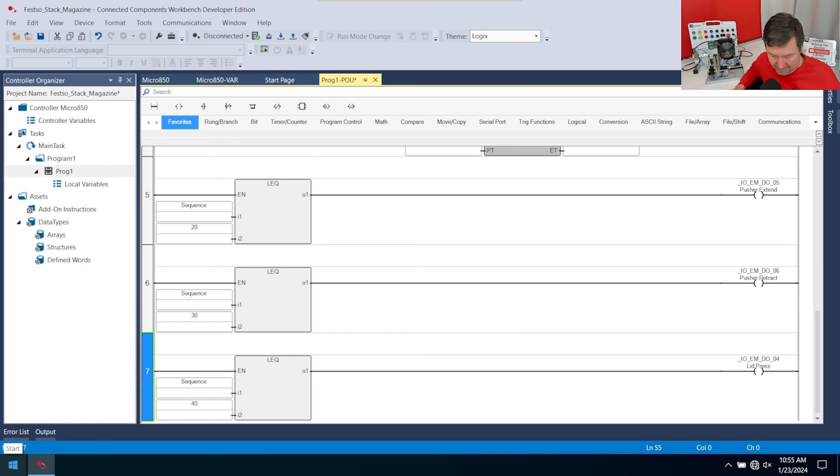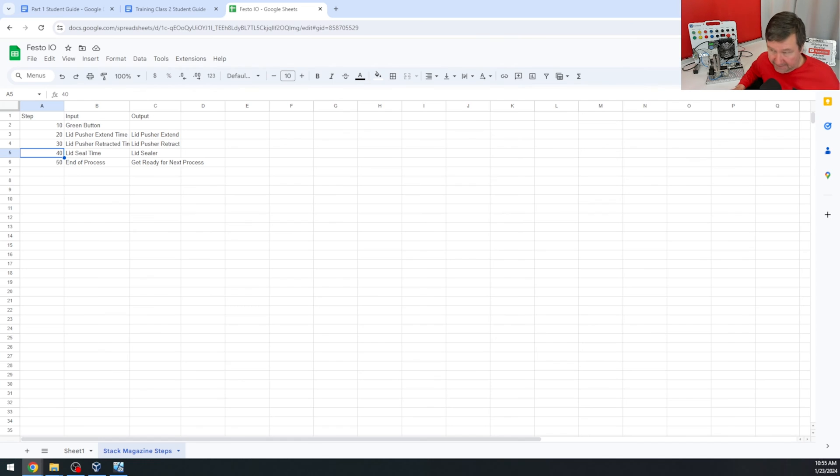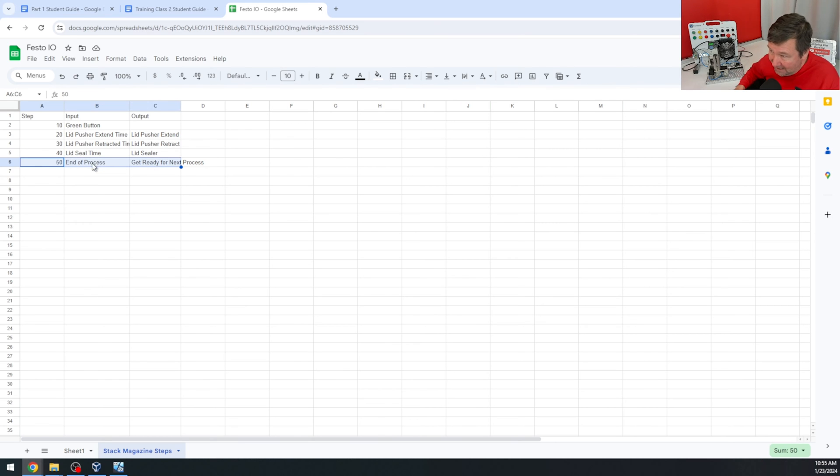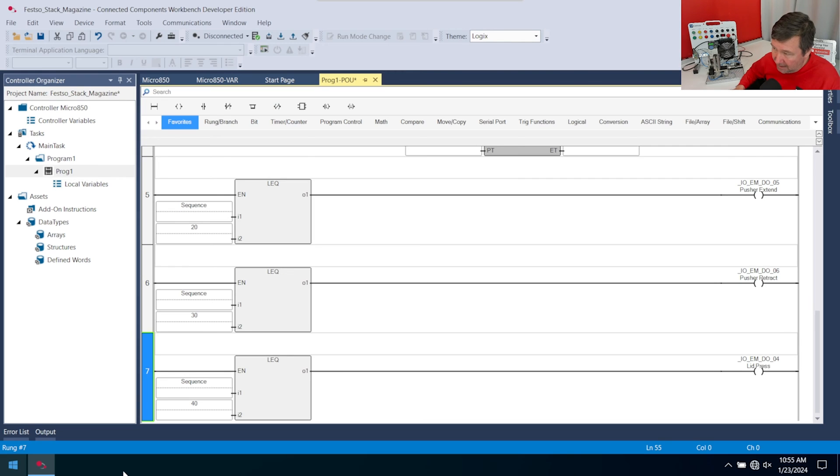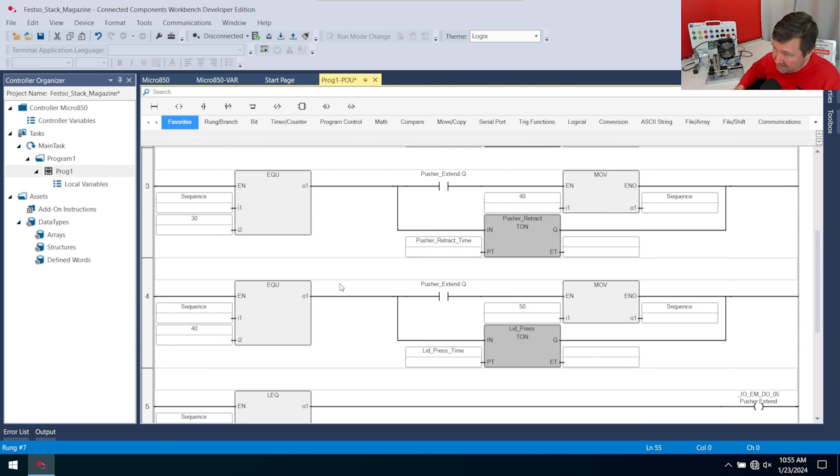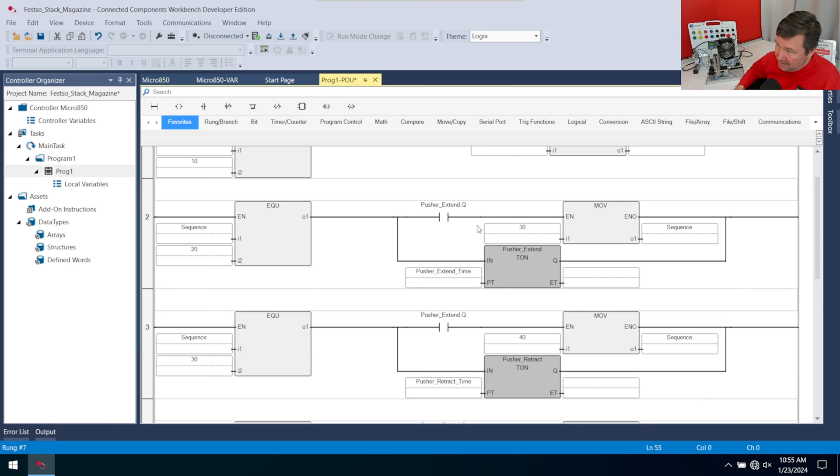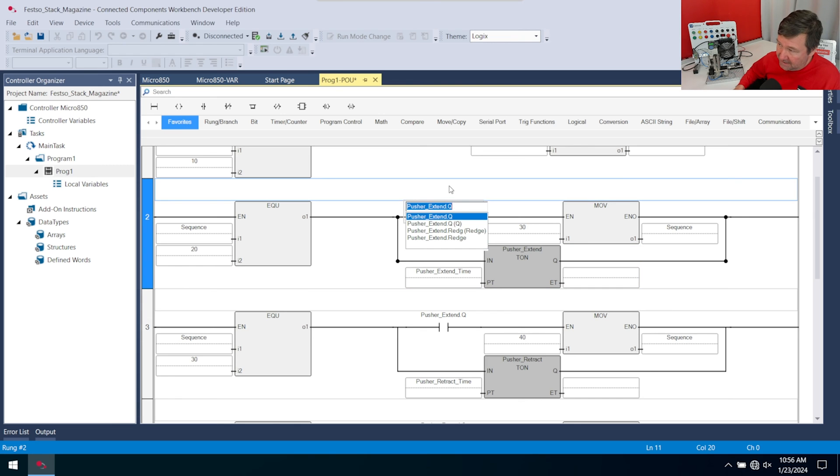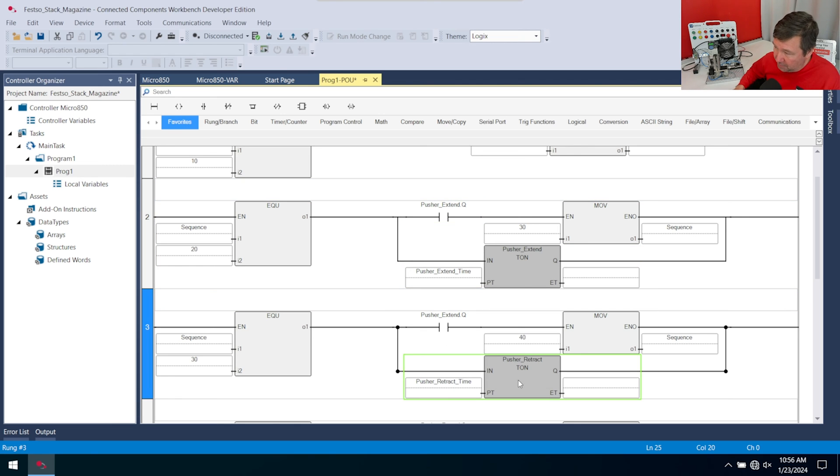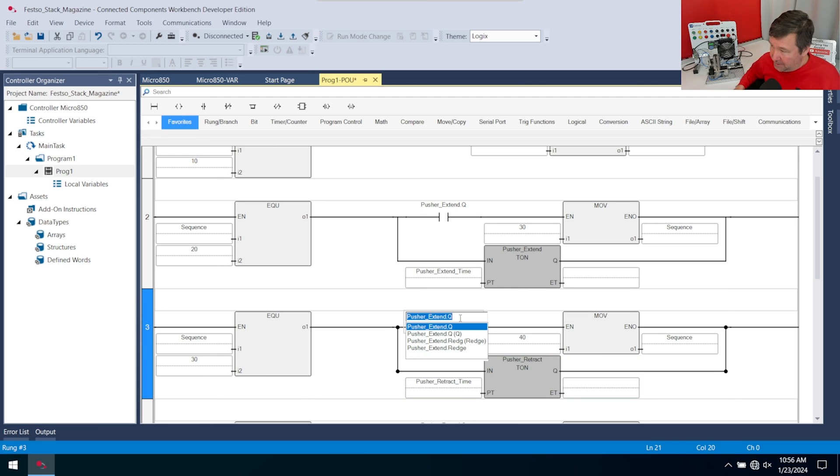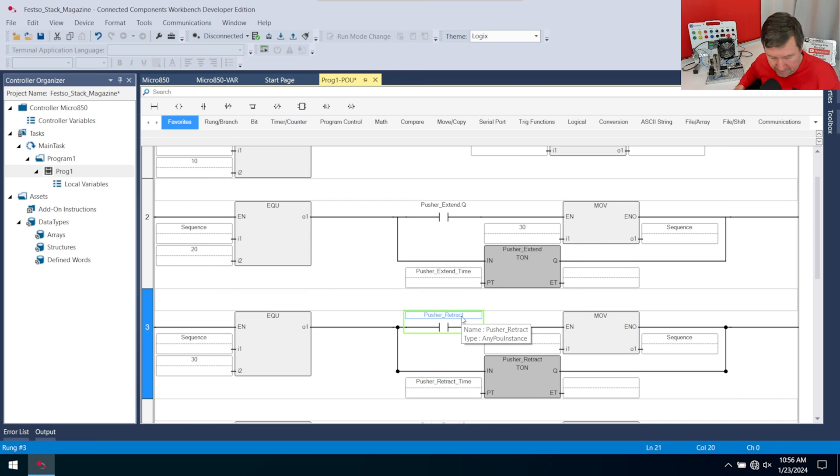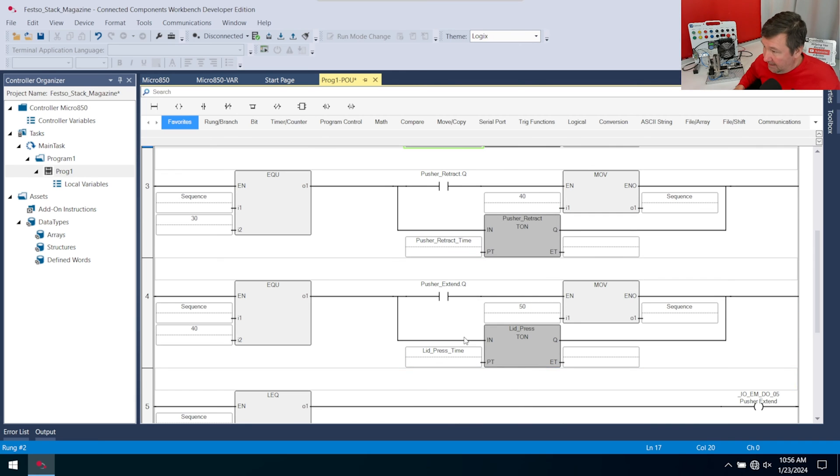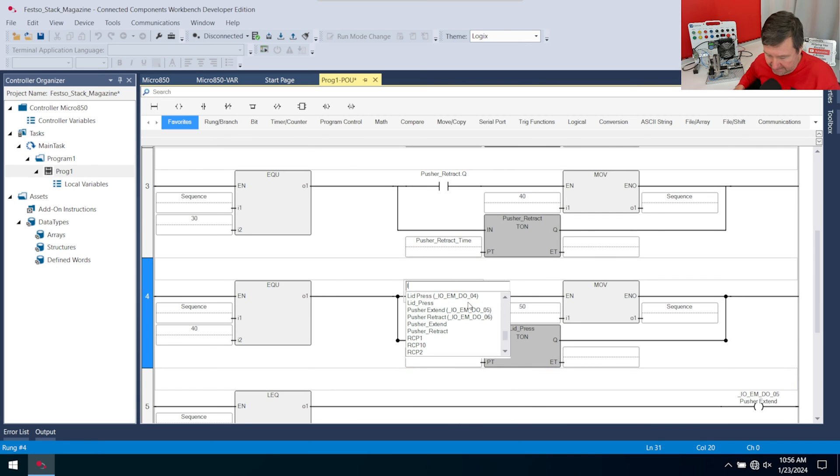Now that gets us through our process, but a lot of you forget this one right here - we need an end of process that gets us ready for the next one. In the case of this one we had a blue button that really reset our sequence, but we want this one to automatically reset. I just realized I made a mistake up here. I changed these timers but I did not change their Qs. We have pusher extend, pusher extend Q. We have pusher retract - we need pusher retract dot Q here. And this one needed to be lid press dot Q.